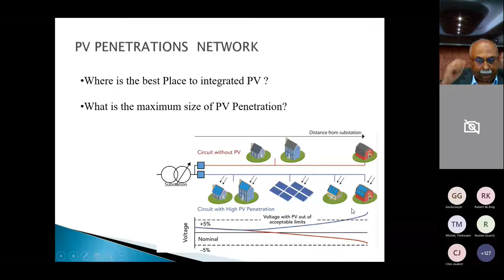We should make sure about that. This is one typical network from Iran. This comes from one substation. We have a lot of feeders, and for each feeder we integrate 10 kilowatt of rooftop PV penetration, which means for a specific location we have around 100 houses, and on top of the roof of each house we integrate and calculate 10 kilowatt. We see in this feeder, especially these houses, we have a violation for the 10 kilowatt. So when we increase the PV, for example from 10 to 15 or 20 kilowatt, we should make sure that all the feeders are within range and there is no violation on the network. If some violation happens, we can manage the violating part.